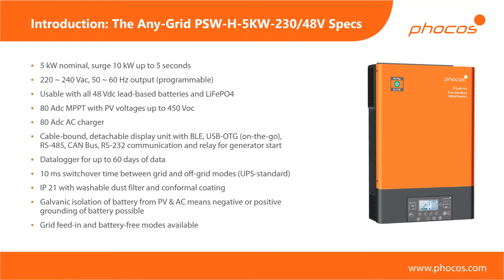So I'll start off with the first point, which is we have a 5 kilowatt nominal power rating. So you can use any types of loads. They can be resistive, inductive, etc. Up to 5 kilowatts. Of course, if you're using things like large motors or different types of loads which are not resistive, then you need to take into account your power factor. So typically what you do is, for example, let's say you have a 1 kilowatt inductive load with a power factor of 0.8. Well, then you simply divide 1,000 watts by 0.8, and that gives you 1,250 watts. So that's the rating you should be using. So you always divide by your power factor to get the correct inverter size for your loads.